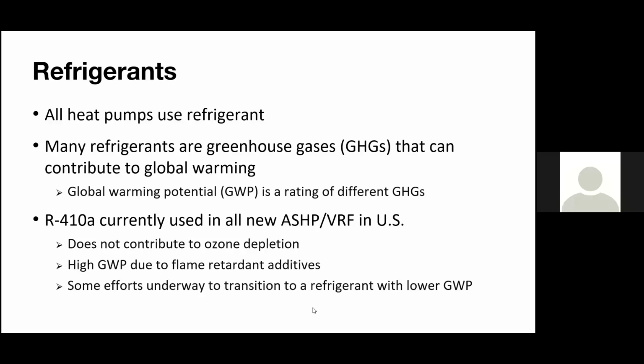So what happens is these refrigerants go up in the air. They do a similar thing that CO2 does when it goes up in the air in the stratosphere in terms of the warming effect. However, due to their characteristics, they're much more stable structures. The strengths of their bonds, they actually tend to have a much greater impact. The GWP of a refrigerant is how much more detrimental to the warming it is compared to the same amount of CO2. So R410A is around 2,000 times worse.